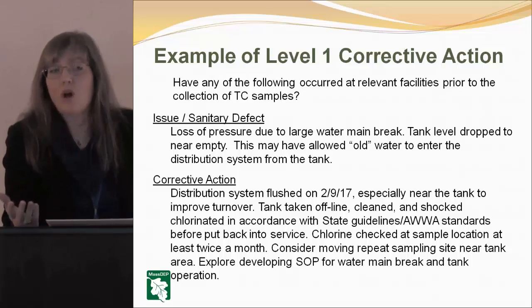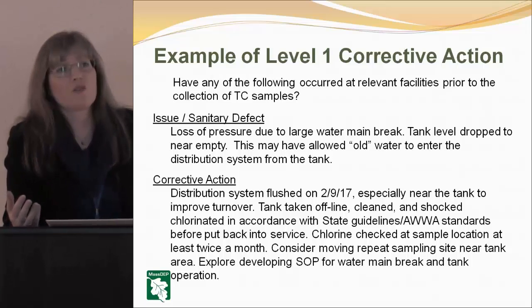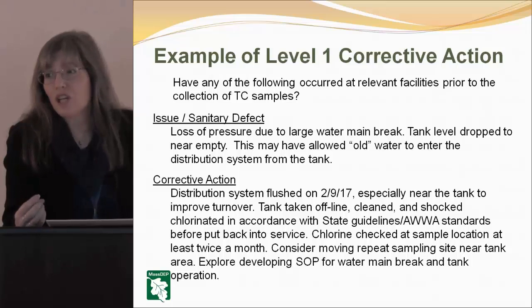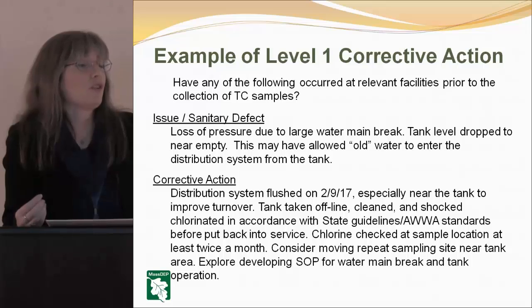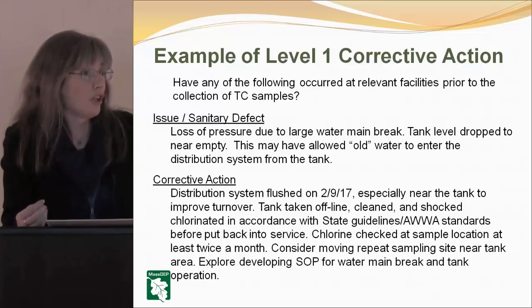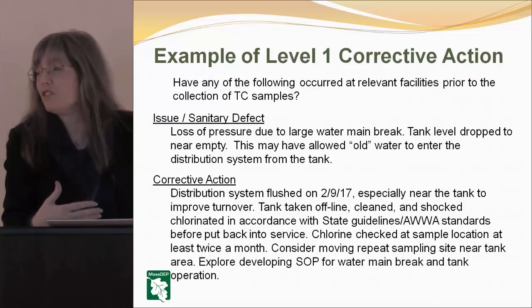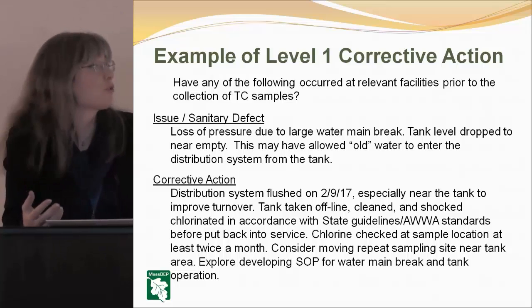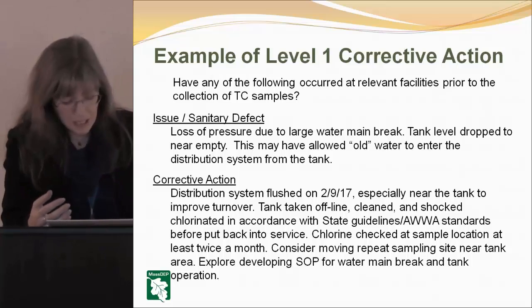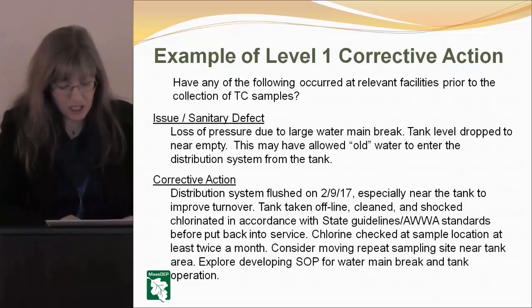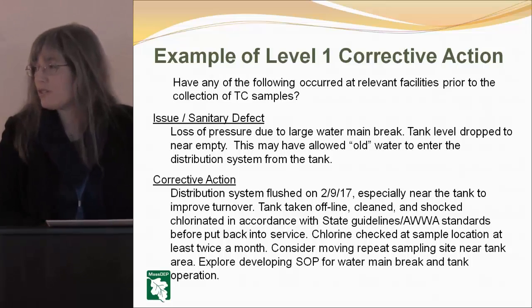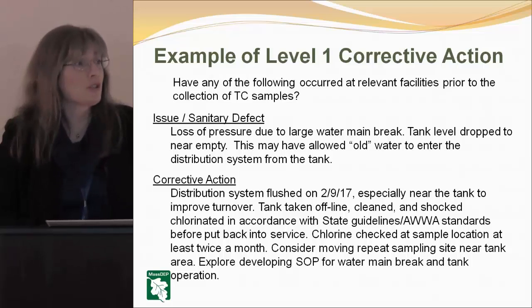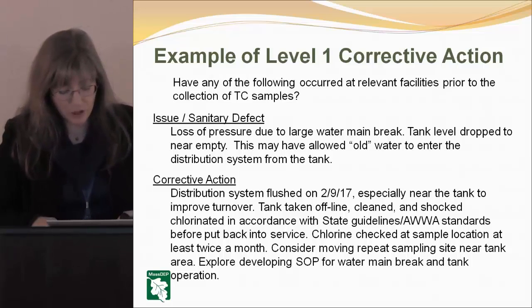So most of you folks that have treatment that have chlorine, you're out checking your chlorine residuals. You know when you start to see a difference in your residuals that you need to adjust your chlorine, especially after detection. You're going to want to monitor your residuals even more closely. You should be checking the sample location at least 2 times per month. Ensure that it's maintaining the residuals that you expect to see at that location.